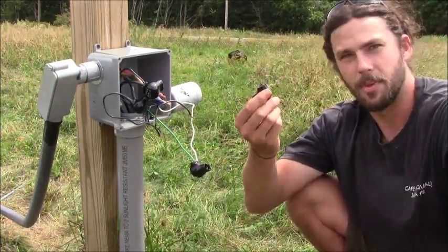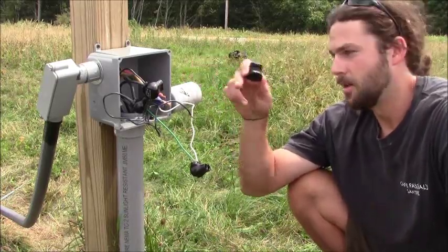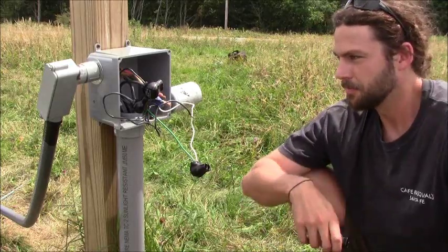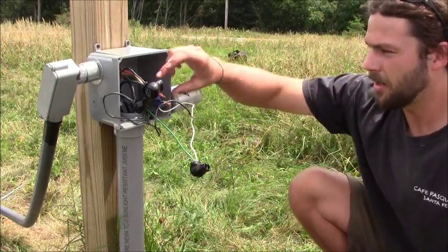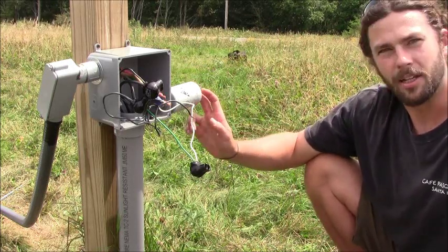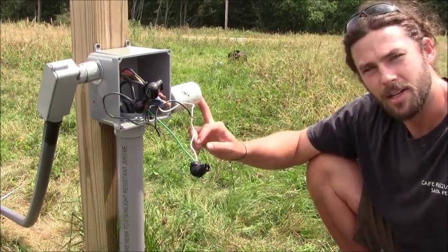In order to do that we'll use these splice blocks, which will act as a splice kit between our SOOW three-conductor wire from the tower and our THWN wire from our control room. In addition to conjoining our three-phase conductors, we're going to include a lightning arrestor here, which acts as our surge protection in case of a lightning strike — this will take the blast and not the turbine.